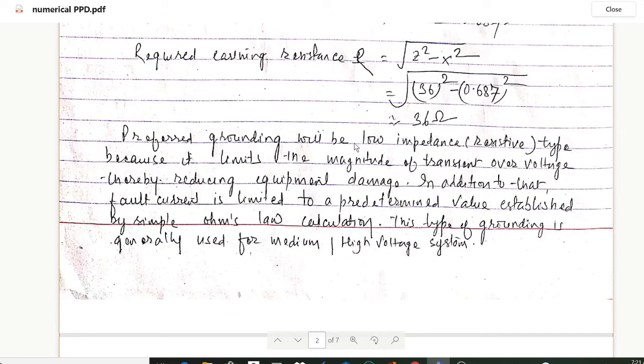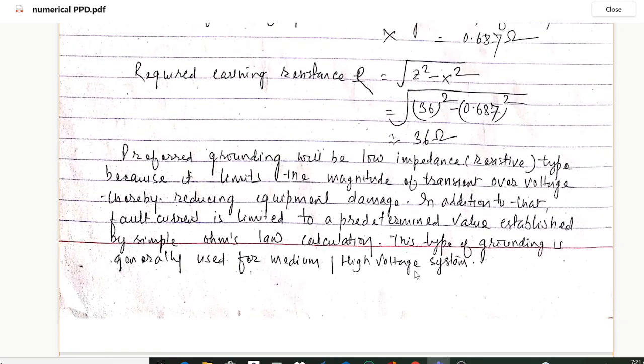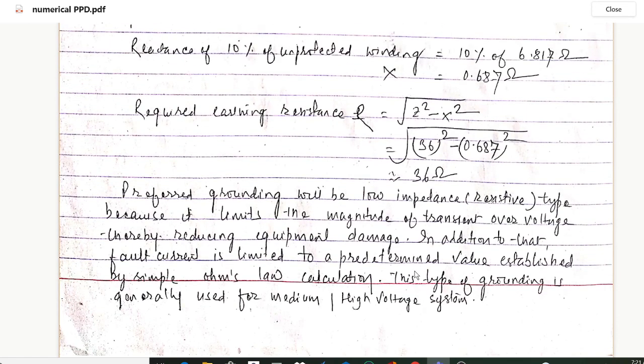Preferred grounding will be low impedance, that is resistive type, because it limits the magnitude of transient overvoltage, thereby reducing the equipment damage. In addition to that, the fault current is limited to a predetermined value established by simple Ohm's law calculation. This type of grounding is generally used for medium and high voltage systems. So in this way you can calculate such type of problems. Hope you enjoyed the lecture. Thanks for watching and please don't forget to subscribe to my channel. Thank you.